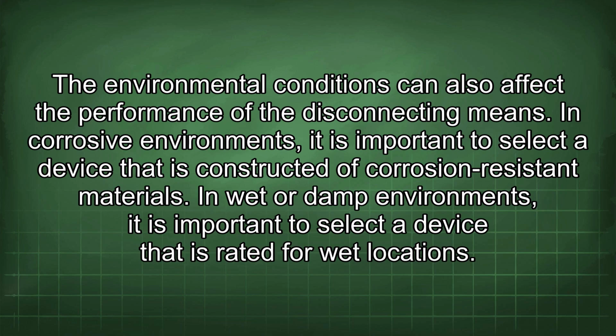The environmental conditions can also affect the performance of the disconnecting means. In corrosive environments, it is important to select a device that is constructed of corrosion-resistant materials. In wet or damp environments, it is important to select a device that is rated for wet locations.